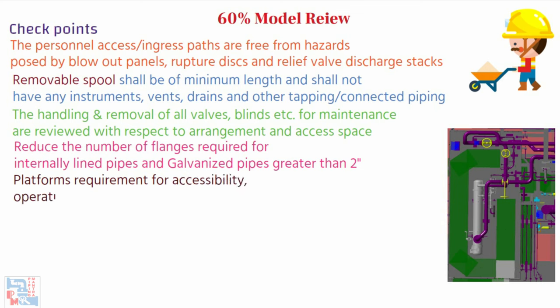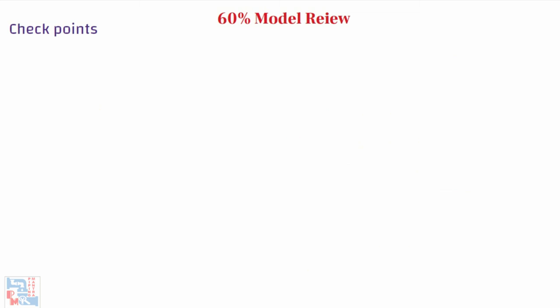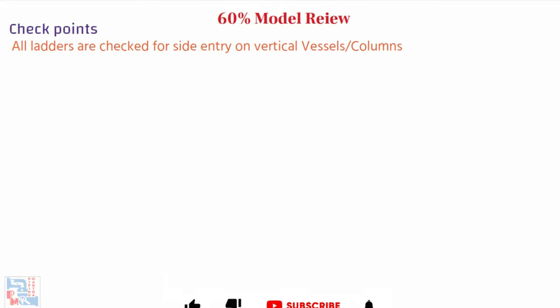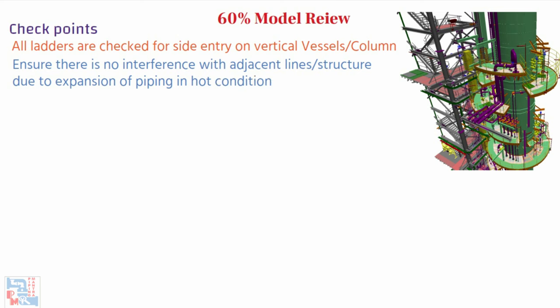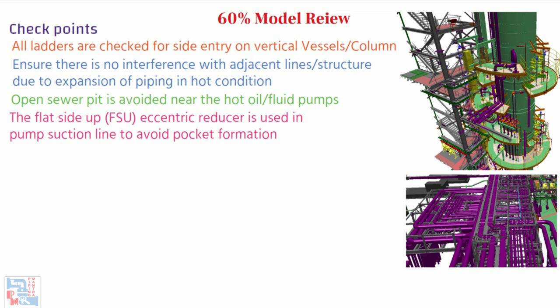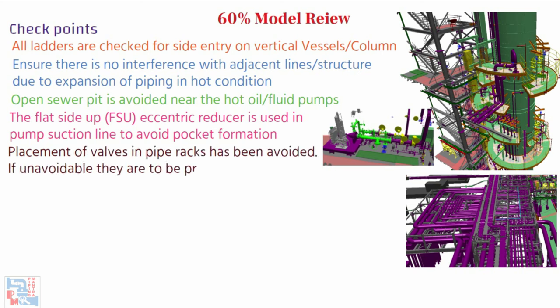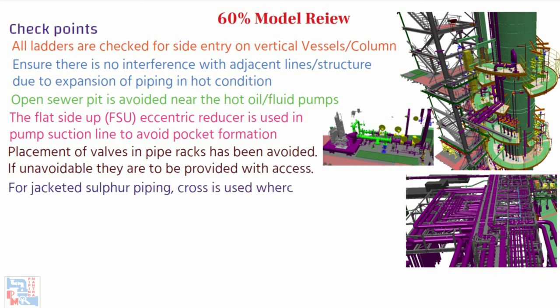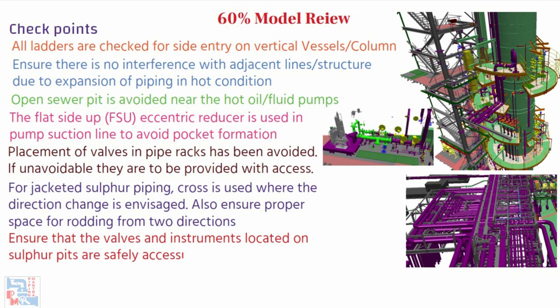Platform requirements for accessibility, operation, and maintenance are taken care of. Proper size cutouts are provided on platform or floor openings for piping. All ladders are checked for side entry on vertical vessels or columns. Ensure there is no interference with adjacent lines or structure due to thermal expansion of piping in hot conditions. Open sewer pits are avoided near hot oil or fluid pumps. The flat-side-up (FSU) eccentric reducer is used in the pump suction line to avoid pocket formation, which may cause cavitation. Placement of valves in pipe racks is avoided; if unavoidable, access for rodding is provided. For jacketed sulphur piping, a cross is used where direction change is envisaged, ensuring proper space for rodding from two directions. Ensure valves and instruments located in sulphur pits are safely accessible in case of fire or shutdown.